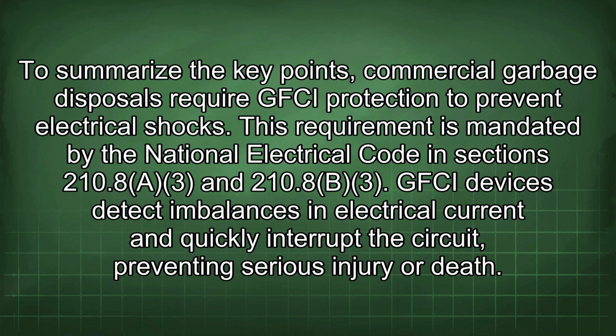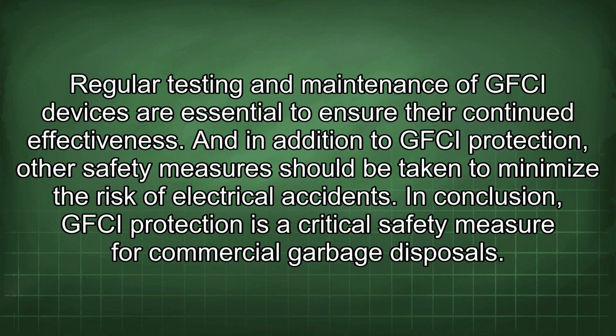To summarize the key points, commercial garbage disposals require GFCI protection to prevent electrical shocks. This requirement is mandated by the National Electrical Code in sections 210.8(A)(3) and 210.8(B)(3). GFCI devices detect imbalances in electrical current and quickly interrupt the circuit, preventing serious injury or death. Regular testing and maintenance of GFCI devices are essential to ensure their continued effectiveness. And in addition to GFCI protection, other safety measures should be taken to minimize the risk of electrical accidents.